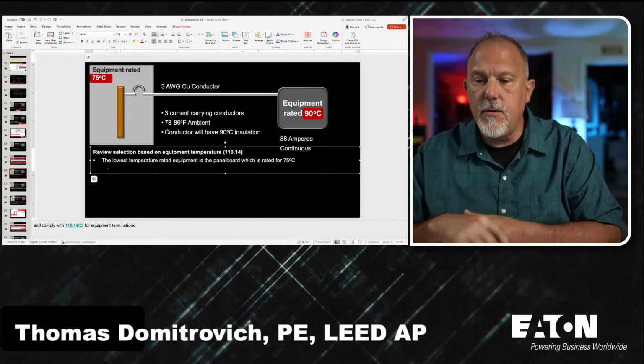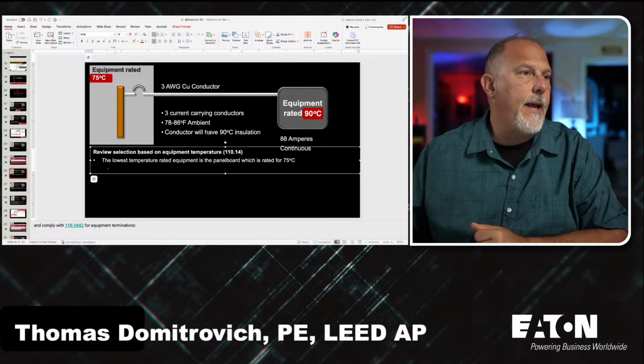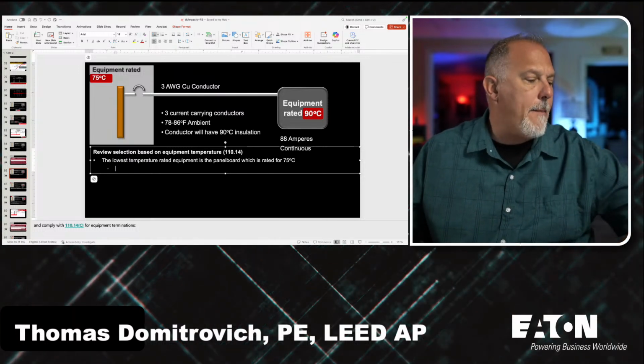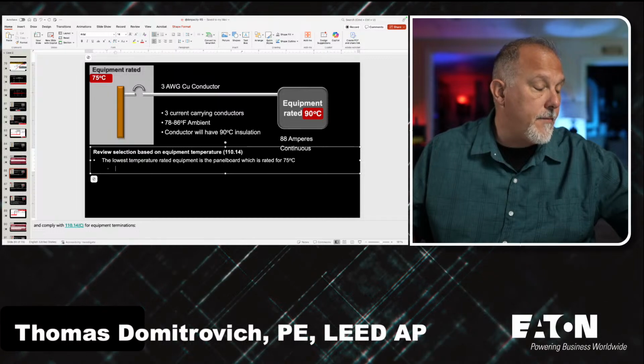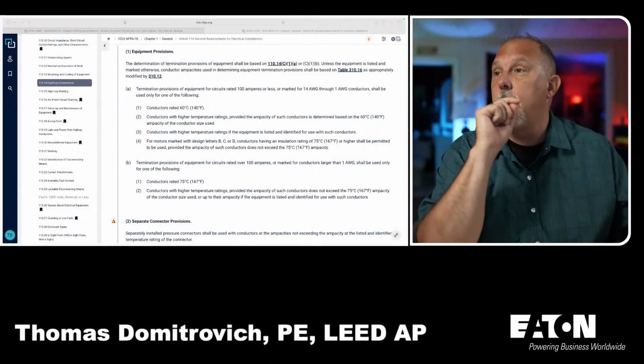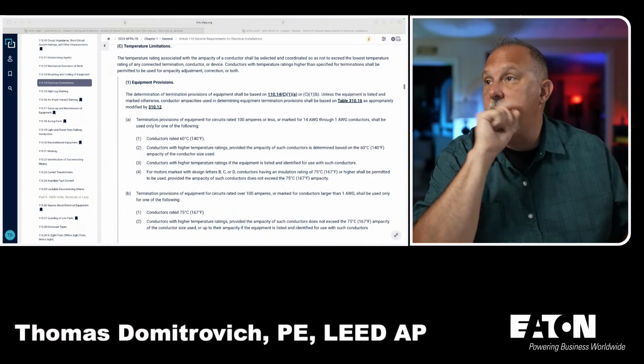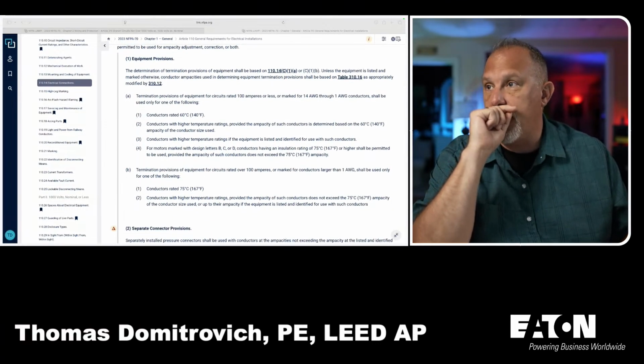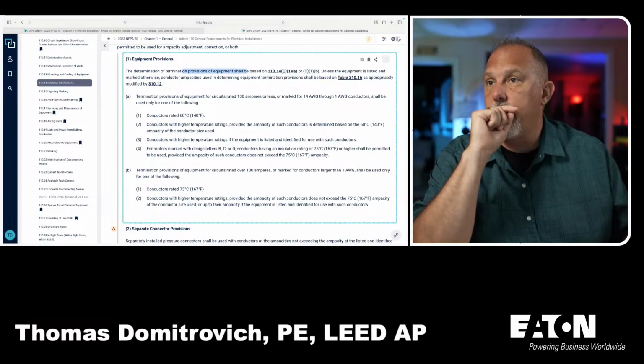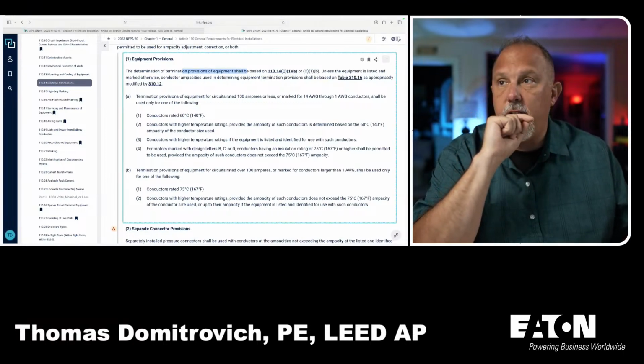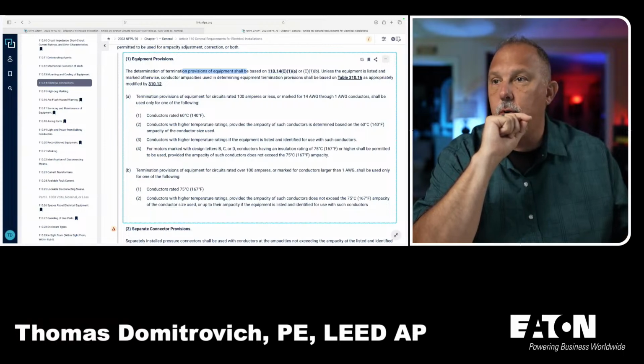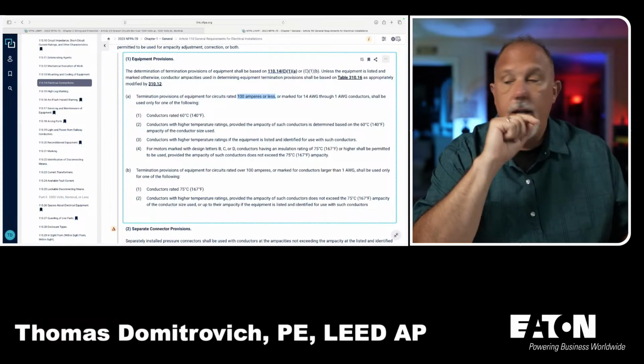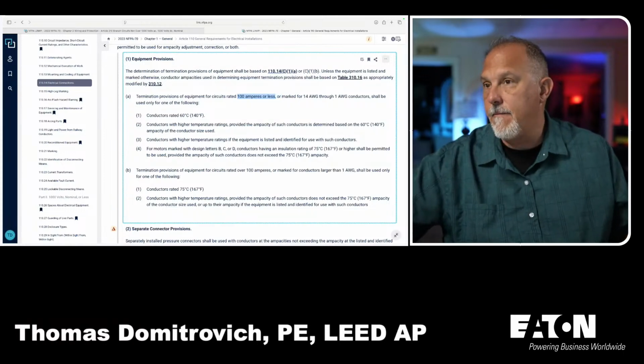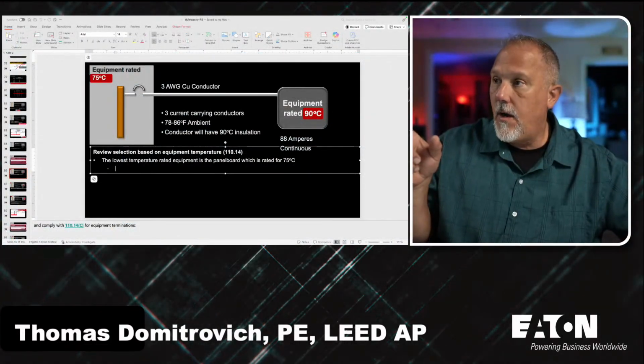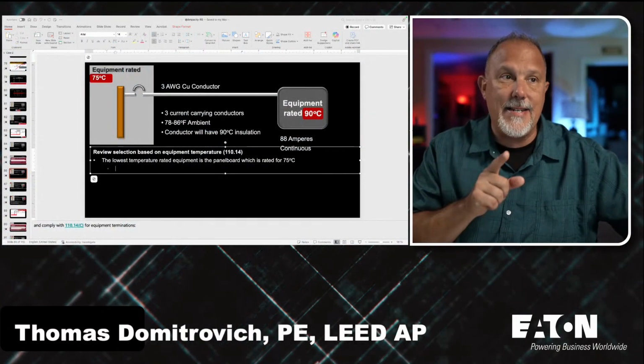for equipment 100 amps or less, here's what I'm going to do. This is 110.14(C), and this is my equipment provisions. What it says is the determination of provisions for equipment shall be based on A or B. Now, A is your 100 amps or less. If I say 100 amps or less, then I have equipment that's rated 90 C.